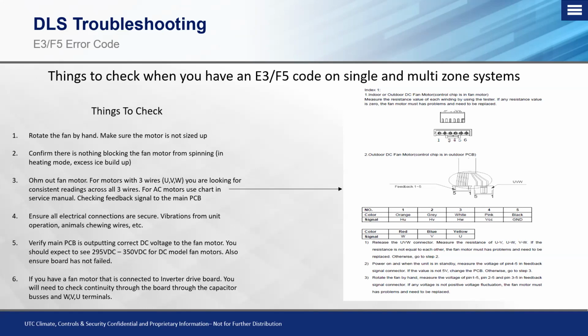You can either see a physical black mark on it, or the board itself is not lighting up. Of course, if the board's not powered, it's not going to send output power to run any compressor or outdoor fan motor. So again, verifying the correct voltage is being sent out from the board, and also ensuring that the board is actually working and is powered, has LEDs, or has a digital screen that is lit up on it. Okay, again, good rule of thumb with that is if you can verify the board is outputting the correct DC voltage, you know that the board's doing its job.